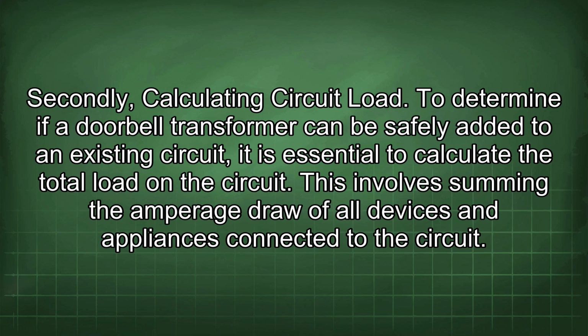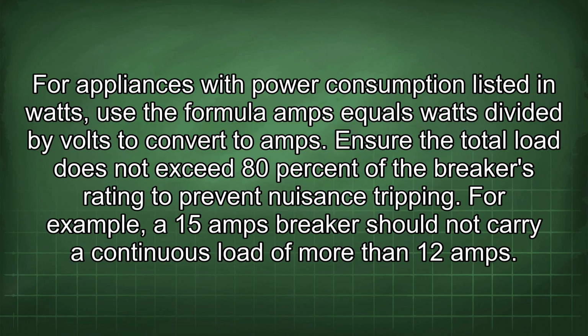Secondly, calculating circuit load. To determine if a doorbell transformer can be safely added to an existing circuit, it is essential to calculate the total load on the circuit. This involves summing the amperage draw of all devices and appliances connected to the circuit. For appliances with power consumption listed in watts, use the formula amps equals watts divided by volts to convert to amps. Ensure the total load does not exceed 80% of the breaker's rating to prevent nuisance tripping. For example, a 15 amp breaker should not carry a continuous load of more than 12 amps.